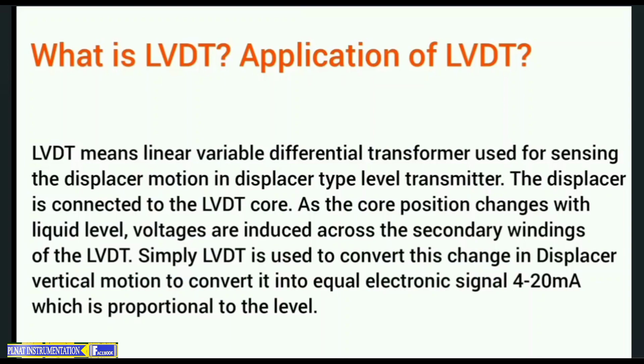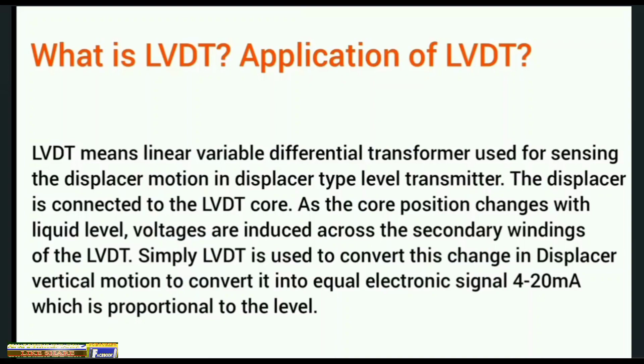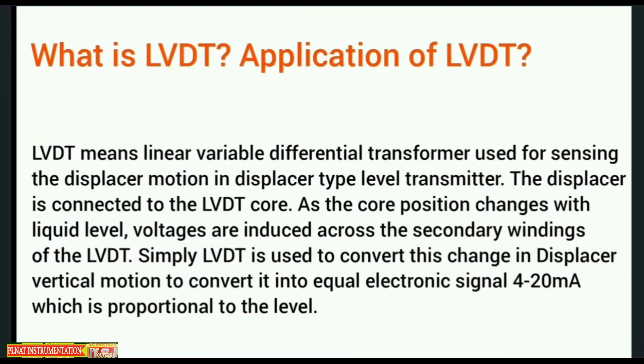What is LVDT and its application? LVDT means Linear Variable Differential Transformer, used for sensing the displacer motion in a displacer-type level transmitter. The displacer is connected to the LVDT core; as the core position changes with liquid level, voltage is induced across the secondary windings of the LVDT. LVDT converts changes in displacer vertical motion into an electronic signal of 4 to 20 mA, proportional to the level.